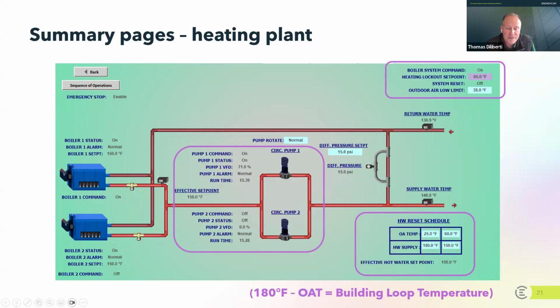The energy event here, though, is you want to make sure that only one of them is scheduled on and the other one is scheduled off. If both of these are scheduled on, it provokes the question, why? Sometimes when it gets really cold, people want to turn both of these pumps on. But in most situations, systems are designed to run either one pump or the other, and running them both redundantly is energy waste. So keep your eye out for redundant pumping and make sure it's being programmed correctly.